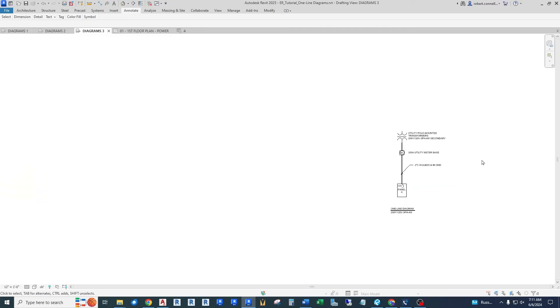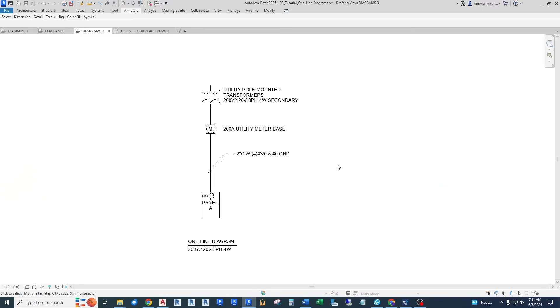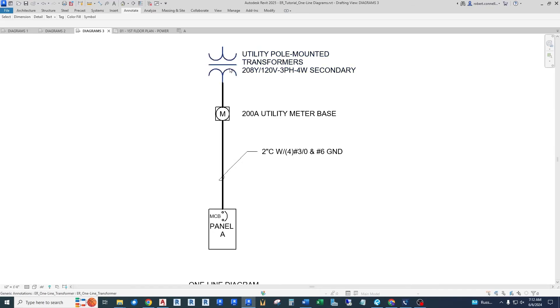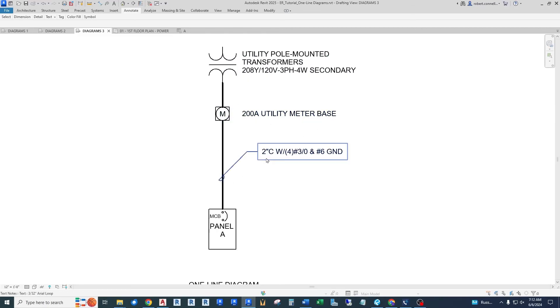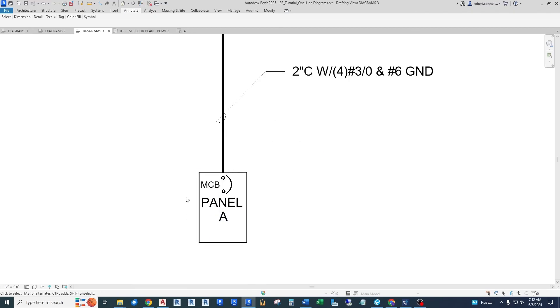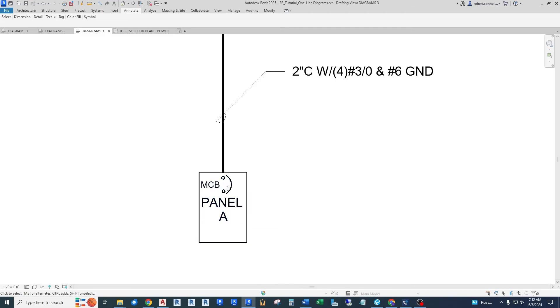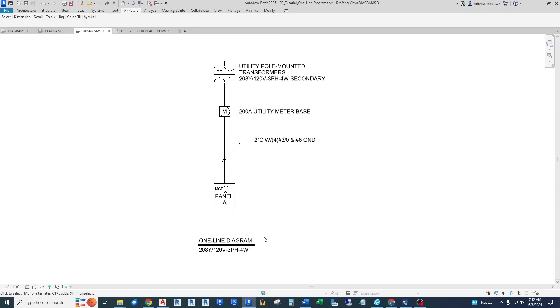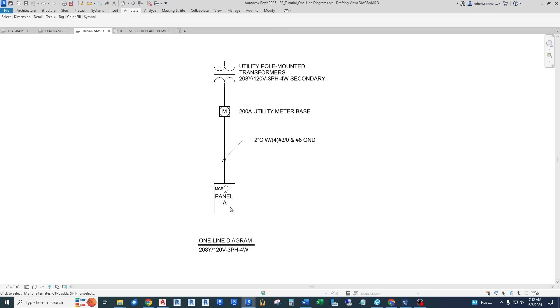And then to show the distribution side, let's go back to our diagrams. The distribution side, we use the one line diagram. So here is that simple source. In this case, we have a utility pole mounted transformers, a bank of those to give us 208Y/120 volt three phase system, a four wire system. And it's going through a meter, self-contained meter base. So we say what size that is. And this shows that we have actually a conduit in this situation. We have a two inch conduit with four number three ought AWG gauge wires and a number six ground. And that comes into this symbol. This box is a symbol for a panel, panel A. And I even have a symbol for the main circuit breaker that is contained within that panel to protect this panel. And so from this diagram, you can easily see how the power goes from the source down through the meter, down to the panel, and then it'll go out to the loads, which we show on the floor plan.